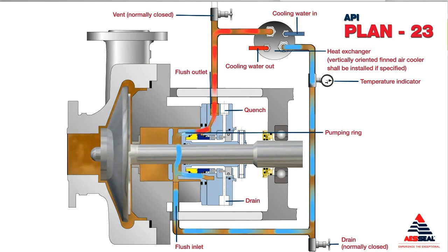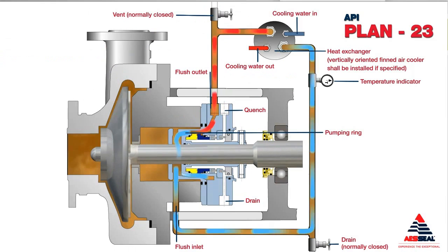This is the Plan 23, and you can see that we're using a pumping ring to basically force that fluid. We're not taking that fluid from the hot pump, from the hot discharge. Instead, we're just recirculating the fluid that's already in the seal chamber. So you can see that through a pumping ring, we raise the pressure and put it into the heat exchanger, cool it down, and then re-inject it back into the seal chamber.